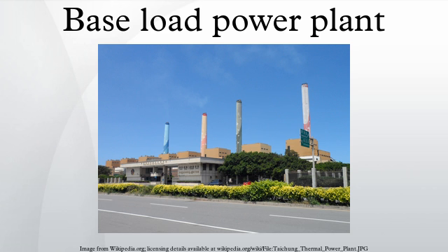Economics: power plants are designated baseload based on their low-cost generation, efficiency and safety at rated output power levels. Baseload power plants do not change production to match power consumption demands since it is more economical to operate them at constant production levels. Use of higher-cost combined cycle plants or combustion turbines is thus minimized, and these plants can be cycled up and down to match more rapid fluctuations in consumption.